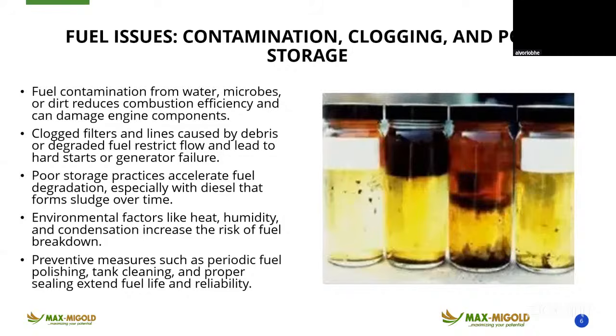This reduces combustion efficiency and can damage engine components. Ensure the diesel going into your generator is clean, and install a water separator to reduce the effect of contaminated fuel. The water separator separates water from diesel based on density - diesel is lighter than water, so it flows on top, allowing the filtered fuel to go into your generator.